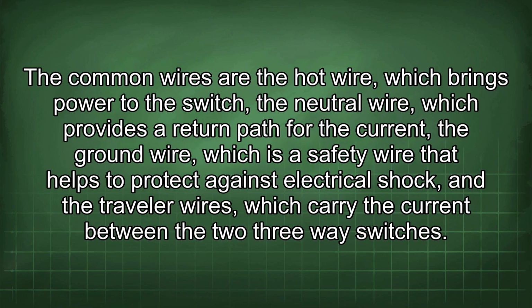The common wires are the hot wire, which brings power to the switch, the neutral wire, which provides a return path for the current, the ground wire, which is a safety wire that helps to protect against electrical shock, and the traveler wires, which carry the current between the two three-way switches.